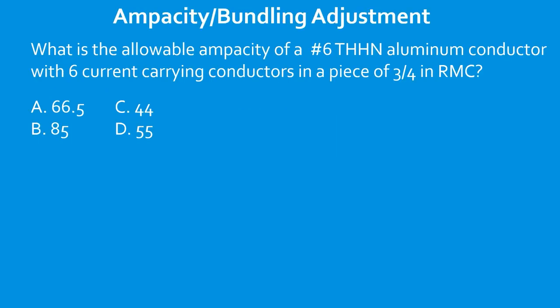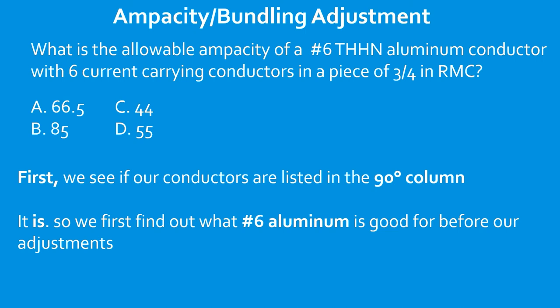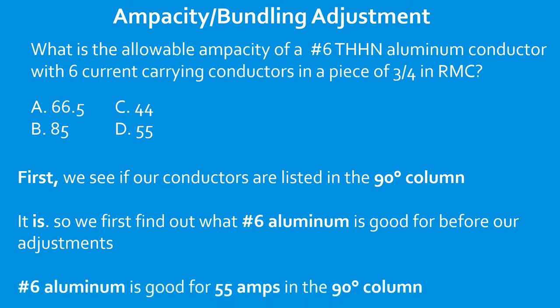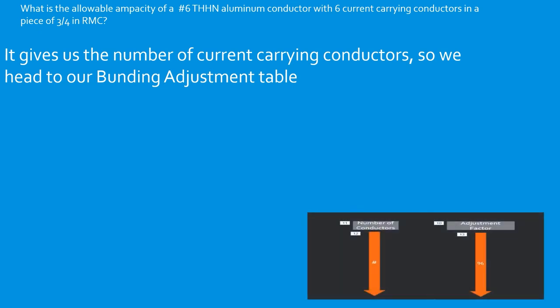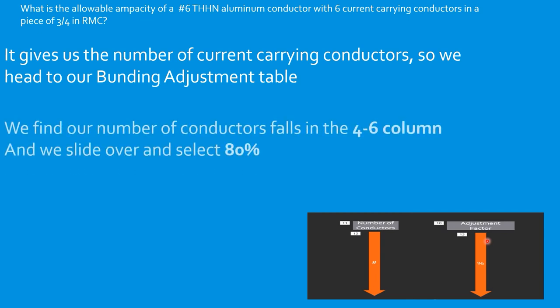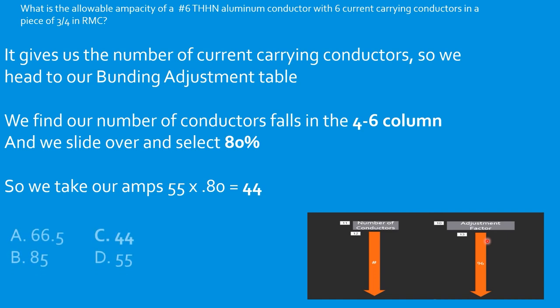Question: What is the allowable ampacity of a number six THHN aluminum conductor with six current-carrying conductors in a piece of 3/4-inch RMC? Confirm THHN is in the 90°C column. Number six aluminum in the 90°C column is 55 amps — be sure to select from the aluminum side. Six conductors falls in the four-to-six range — adjustment factor is 80%, or 0.80. So: 55 × 0.80 = 44 amps. Select C.